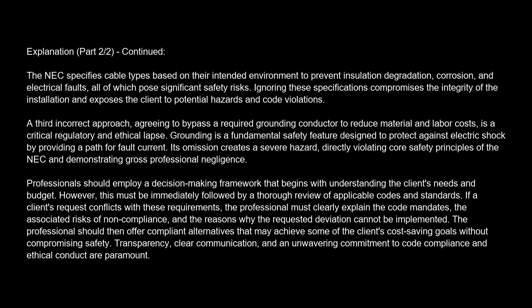A third incorrect approach, agreeing to bypass a required grounding conductor to reduce material and labor costs, is a critical regulatory and ethical lapse. Grounding is a fundamental safety feature designed to protect against electric shock by providing a path for fault current. Its omission creates a severe hazard, directly violating core safety principles of the NEC and demonstrating gross professional negligence.